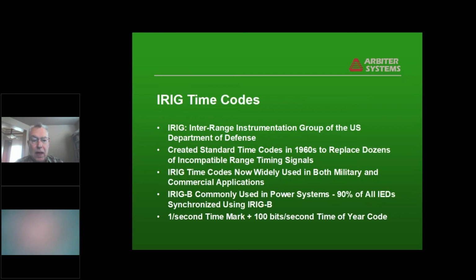IRIG time codes. IRIG stands for Interrange Instrumentation Group. It's an agency of, or smaller than an agency, I don't know what they call it, a division or whatever of the US Department of Defense. And they created standard time codes back in the 1960s because every range had its own time signal that they were using. And what they did with these things was they would generate this signal in the audio band of basically a modulation on a 1 kilohertz tone typically, and it could be recorded on an instrumentation tape recorder, along with data coming from transducers when they do a test on a range, you know, a missile shooting down a drone or something like that.